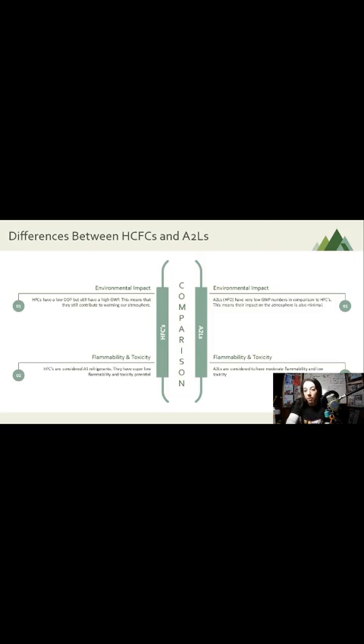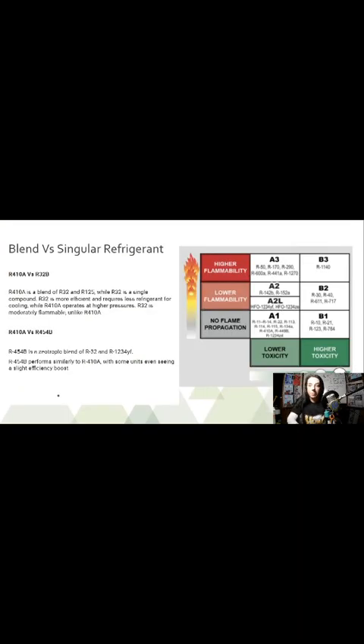Flammability and toxicity: HFCs are considered A1 refrigerants. They have a super low flammability and toxicity potential. And A2Ls still have almost no toxicity whatsoever. And they're considered moderately flammable. And when I say moderately, I mean you have to hold a torch on them to get them to burn. If you remove the torch, you remove the burn. Problem is, there are other materials around that refrigerant, right? So sometimes it can catch a wire, and wires are flammable, right? So it's not so much that the refrigerant within the unit is flammable. It's more that when the flammable refrigerant leaks out, it can catch other stuff if there were a spark. So that's what we need to be careful of. And I will tell you how we're being careful too.